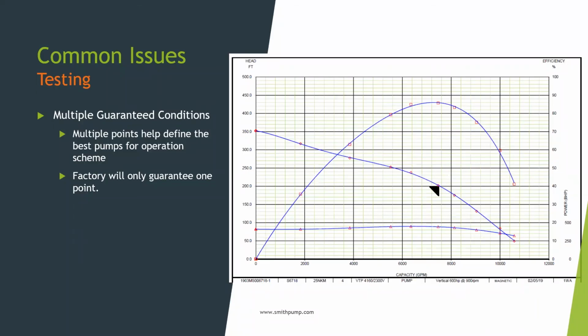So let me cover a few quick points on pump testing. We've seen some specs ask us to guarantee multiple design points on a pump. It's usually good to see multiple points called out on a spec because that helps us pick the closest matching pump curve to the shape defined. However, the factory will only guarantee 1 point during factory testing. The impeller can only be 1 diameter, so there can only be 1 point to hit. The factory can test at multiple points, but only 1 will be guaranteed.